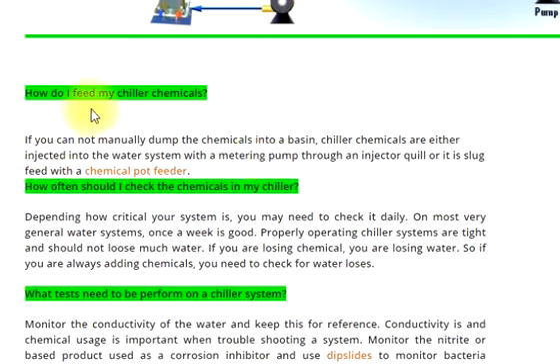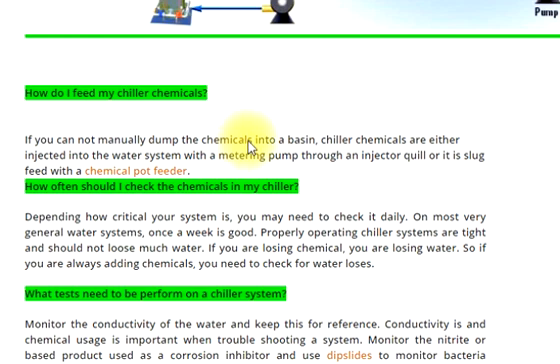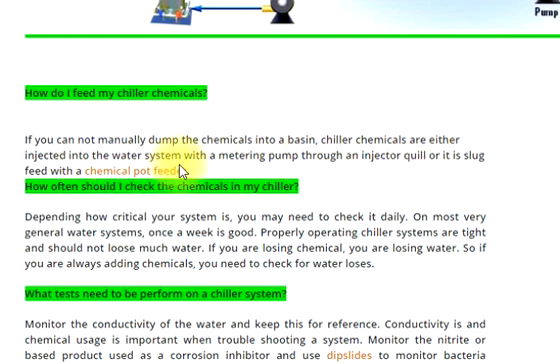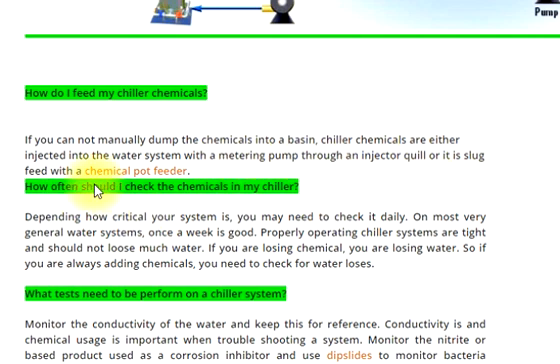How do I feed my chiller chemicals? If you cannot manually dump the chemicals into a basin, chiller chemicals are either injected into the water system with a metering pump through an injector quill, or slug fed with a chemical pot feeder.